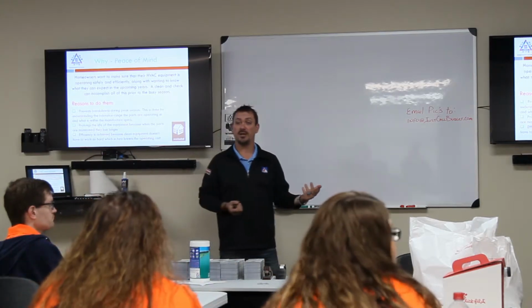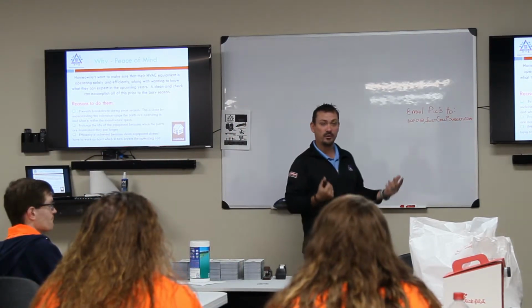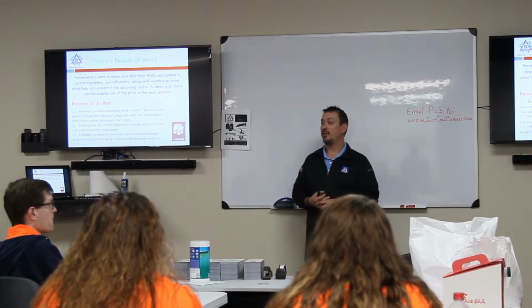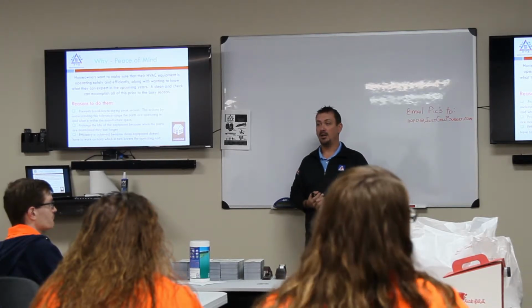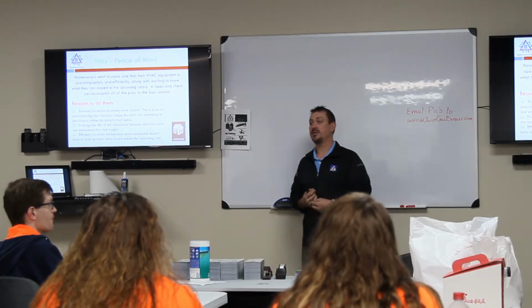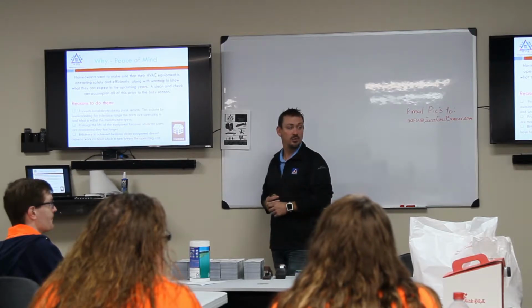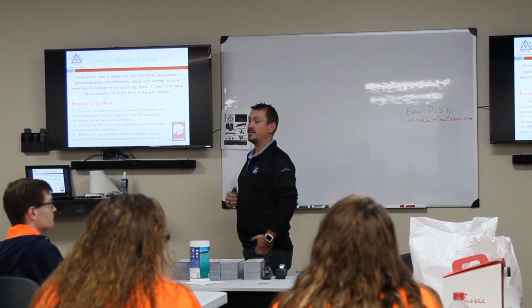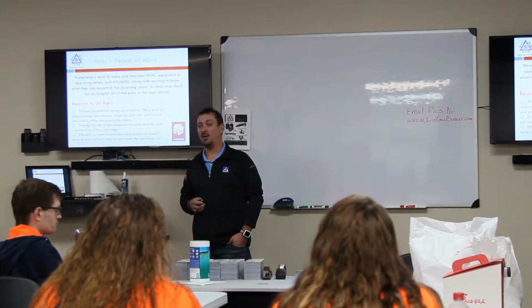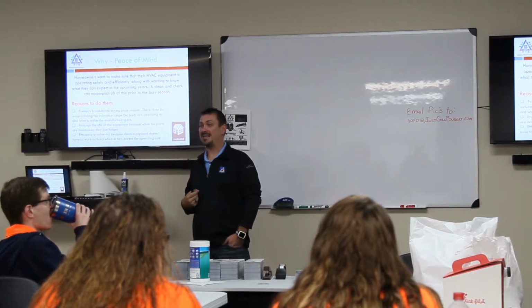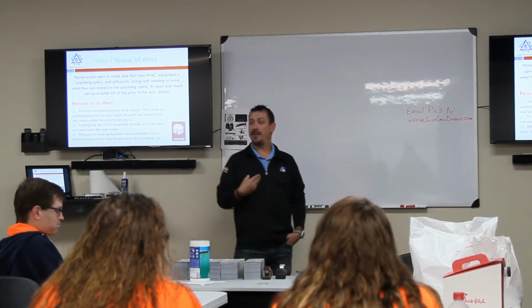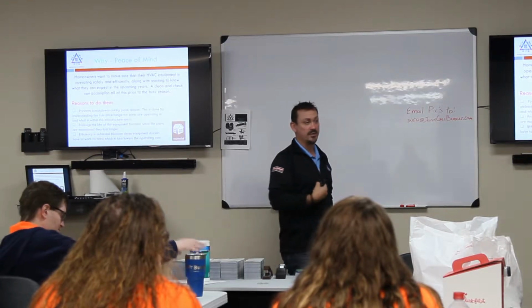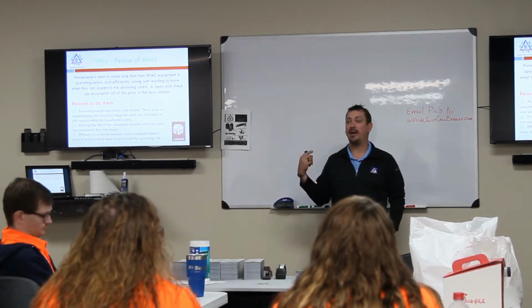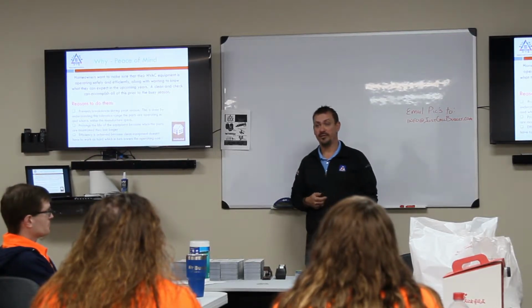Now, if you do a clean and check, can the furnace still break down when it's 20 degrees outside? Of course it can. There are some things that we can't foresee or see that's going to cause an issue, but there are lots of things that we can look at and tell, okay, this has a potential of failing, and that's when we can recommend a replacement of that component. We'll talk about that and go over these components here in a minute.